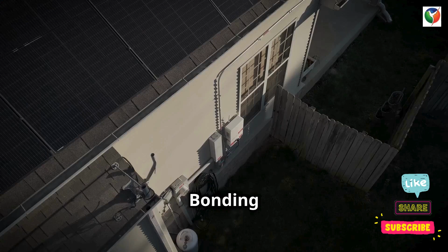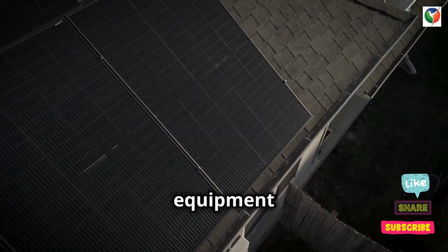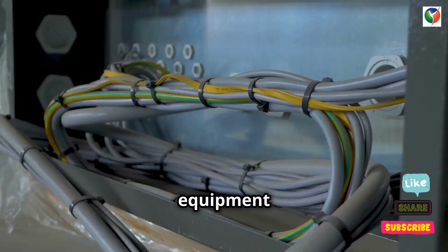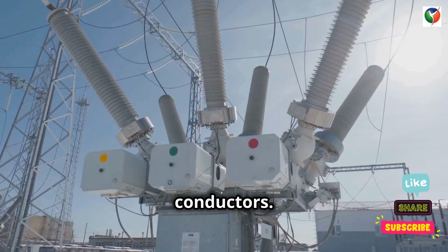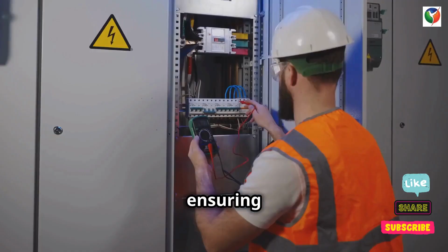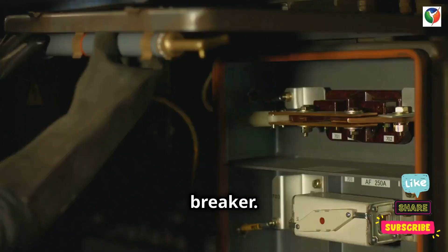Example of bonding. In an industrial facility, all metal enclosures, such as equipment cabinets, conduit, and metal structures, are bonded together using bonding conductors. This ensures that if any metal part becomes energized due to a fault, the potential difference between metal parts is minimized, reducing the risk of shock and ensuring the fault current flows back to the electrical source to trip the breaker.